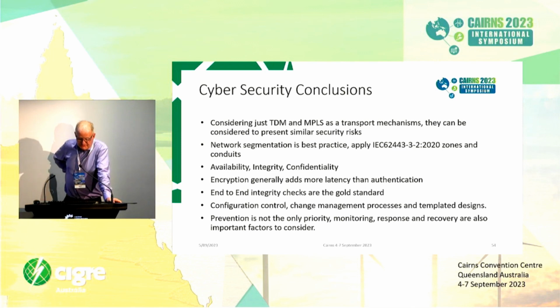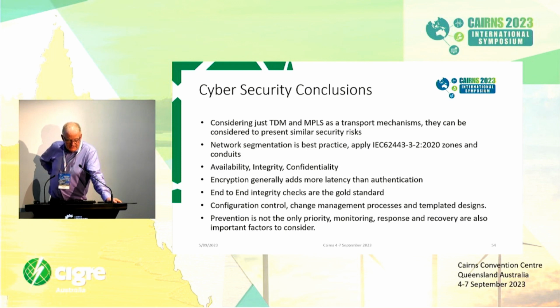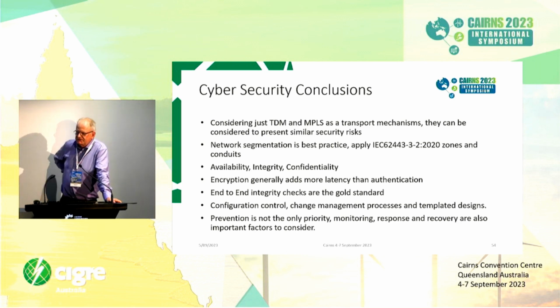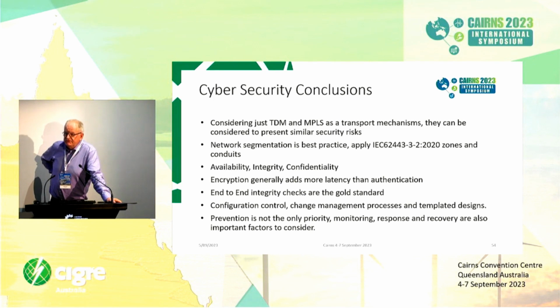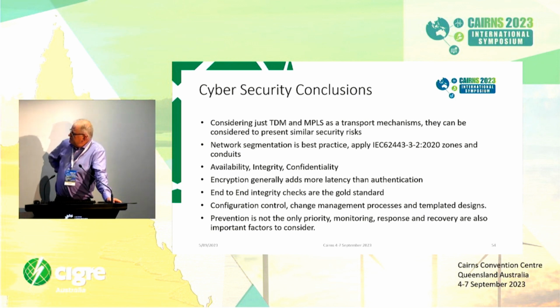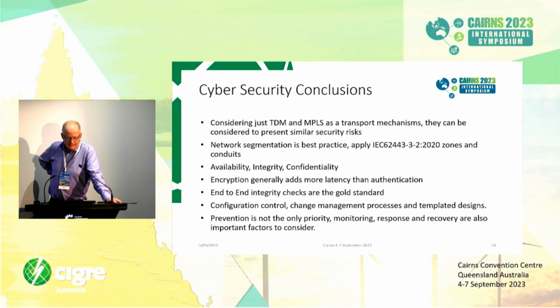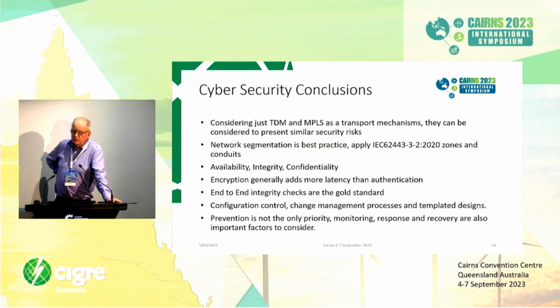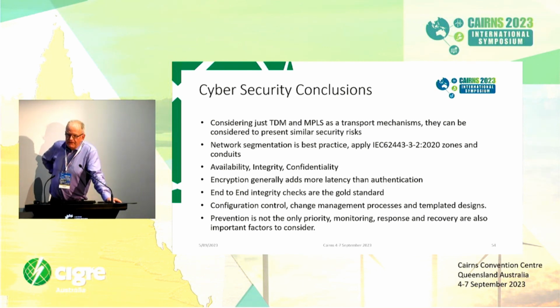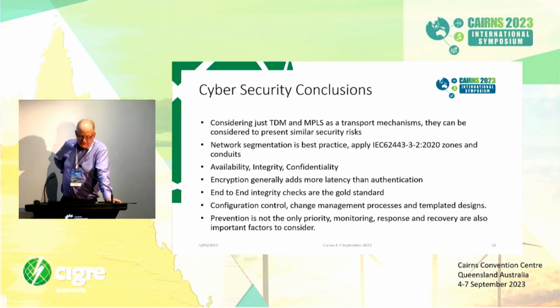For OT systems, substation systems, we flipped the generalised IT security concepts of confidentiality, integrity and availability on their head. So for OT systems, availability is the most important aspect. We need to make sure all of our protection systems and control systems are operating and as close to 100% available as we can get. Also, integrity is important. We can't afford to have the integrity of the teleprotection system compromised, and probably confidentiality not so much.